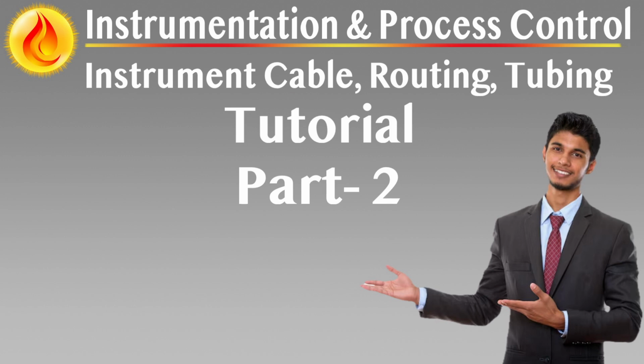Riser points exposed to vehicular or equipment traffic require mechanical protection structures to prevent impact damage. Underground multi-core cable routing is preferred where feasible, as it provides superior protection against mechanical damage, UV degradation, and fire. Underground routes must maintain defined separation from power or lighting cables, typically a minimum horizontal distance of 0.3 meters, and right-angle crossings are mandated for EM immunity. Separation from buried hot pipes must account for thermal degradation, calculated as 0.2 meters plus 0.1 meters per 100 degrees Celsius of pipe surface temperature.